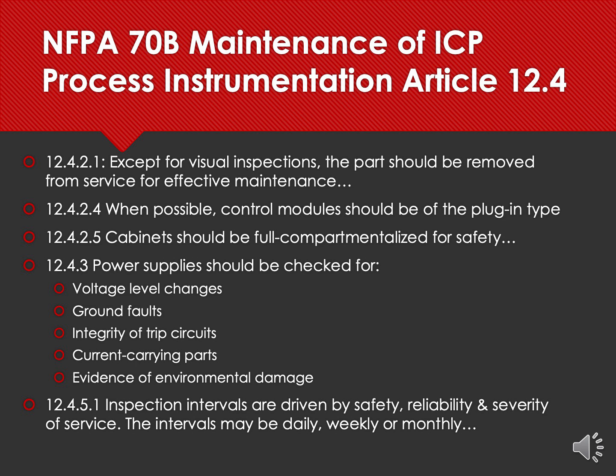The next section talks about the idea of fully compartmentalized for safety. And what they're saying here is that we use compartmentalization to isolate the dangerous parts of the equipment from the not so dangerous parts of the equipment if possible. Other electrical regulations use the term effective isolation for the same concept. And this is, of course, a design change. We design and build the panel with that thought in mind. Power supplies need to be checked for what you see in yellow here on the slide. The voltage level changes. This presupposes that we know what the normal voltage levels are of the equipment. And if they've changed, and we can't attribute it to something obvious, like a change in voltage from the utility, then of course we'd want to figure out what's going on. That may be indicating that the system is beginning to fail.